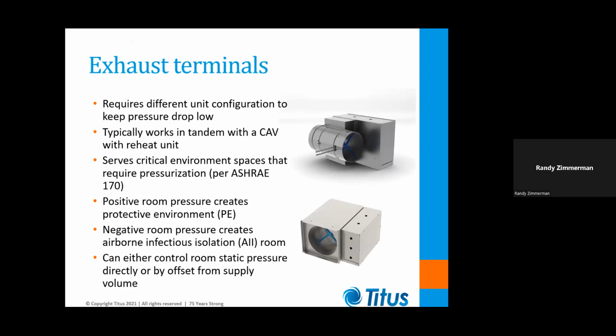Now, exhaust terminals. Exhaust terminals are used typically in critical environment spaces, just like where we would use that constant volume VAV box, because if we're going to try to control the pressurization in the room, then we've got to be able to control the air flowing into the room from the supply box, but also control the air flowing out of the room with an exhaust box. So like we said before, positive pressure creates the protective environment, negative room pressure creates an isolation room. Typically, the way this is done, the supply box handles constant volume with reheat, and then this exhaust box usually maintains a set offset in airflow control to either be slightly higher or slightly lower than the supply volume to create that negative or positive pressure in the room.